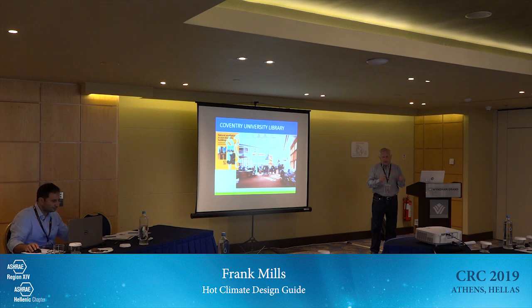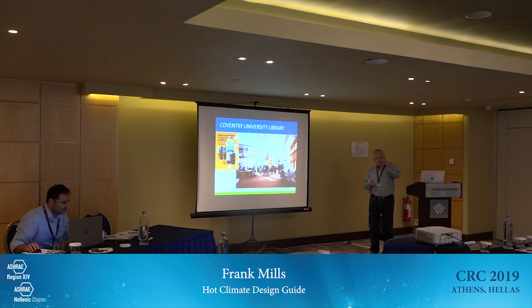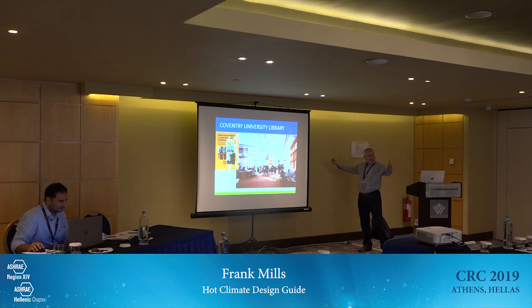the openings better. So if, for example, in this room, we decided on natural ventilation, but those windows were locked or maybe they never open, maybe they're just a piece of glass. We could, underneath the window, put an inlet with a damper, with a controller, so we can measure the temperature in the room here, and that damper would open and close to let more or less air in. This controller could also measure the CO2 in the room, and it could decide we need some more fresh air, so it could open the damper for other reasons.